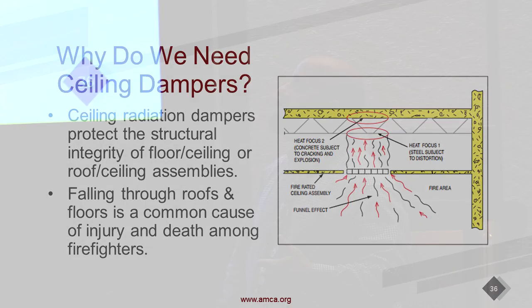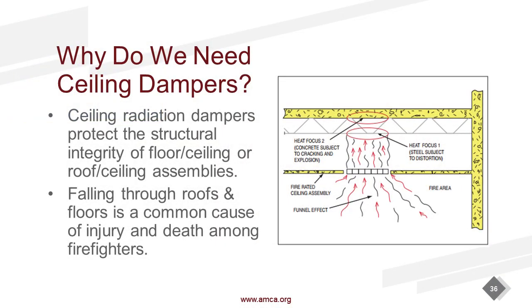I've got a fire-rated ceiling assembly. That diffuser, that air outlet, that place in that T-bar, is a break in the continuity of that ceiling membrane. So the radiation damper, in conjunction with possibly a thermal blanket, makes up that continuity and protects the structure above it: steel truss from cracking and warping, concrete from exploding, wood truss from combusting. Obviously, firefighters can fall through roofs and floors. It's a major killer in the firefighter community. If you think about single-family homes and how many firefighters fall through those roofs, those are wood trusses.